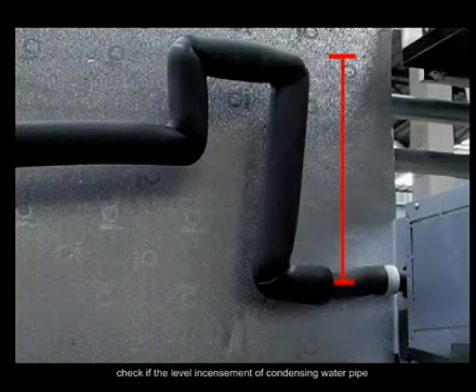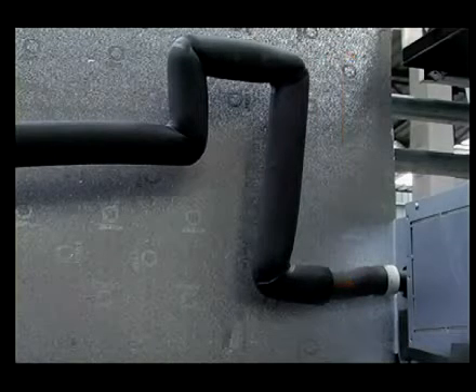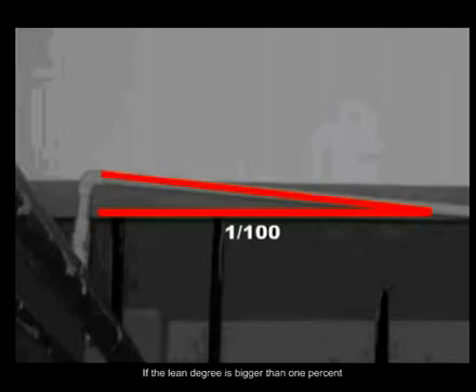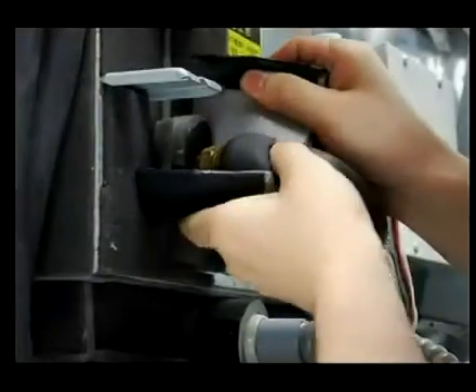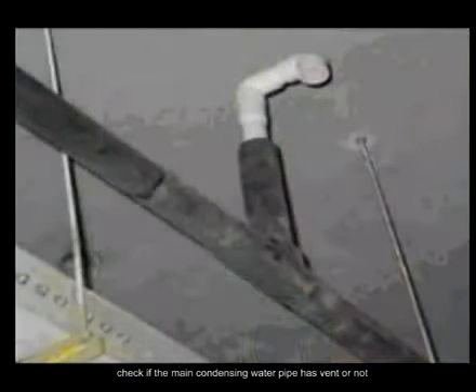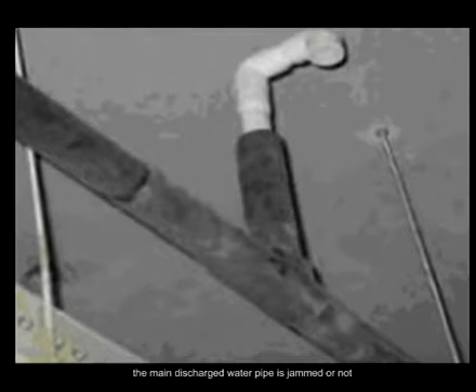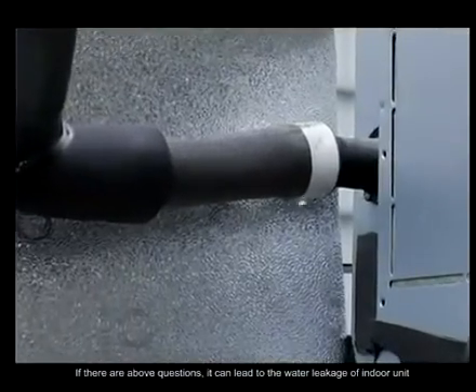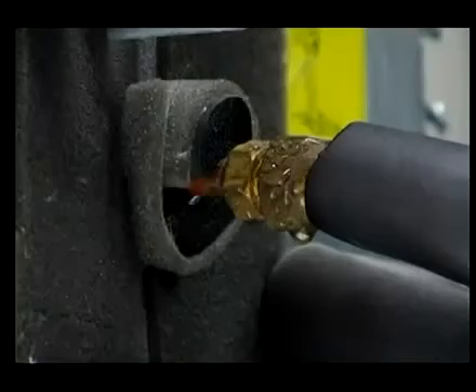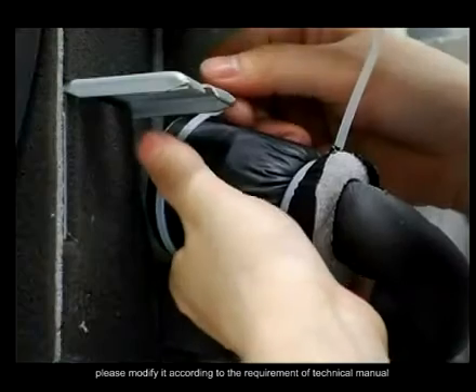Step 3. Inspect if the drainage pipe installation has a problem. Check if the level and slope of the condensing water pipe are out of the standard range or not. If the draining pipe is jammed, the condensing water cannot be discharged. Check if the lean degree is bigger than 1%, and if the pipe connector and throttle part are well heat insulated. Check if the main condensing water pipe has a vent or not. Check if the main discharged water pipe is jammed, which causes the condensing water to not be discharged. If there are the above problems, it can lead to water leakage of the indoor unit. Please modify it according to the requirements of the technical manual.